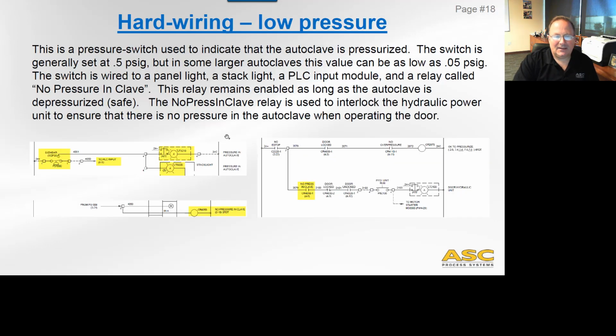So, and then another very important one that we talked about is the low pressure switch. This is a pressure switch used to indicate the autoclave is fully depressurized. It's not triggered at 0 psi, but it's triggered at about a half a psi. In some very large autoclaves, we have a much bigger pressure switch, and that will actually actuate at a very, very low pressure, like 0.05 psi. The switch is wired to the panel light, a stack light, PLC input, and the relay called no pressure in clave. So there's our special relay, no pressure in clave, and again, that would then be used in the hydraulic circuit to keep the hydraulic from ever being able to operate unless we have no pressure in the clave. Okay, so that again is a maintained relay. This relay is maintained when everything is safe, when the pressure switch is down. Okay.